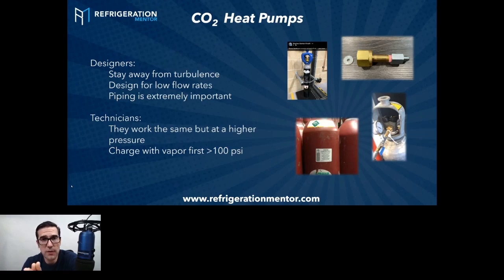In the buffer tanks - assuming you know how heat pumps are designed - you have cold water at the bottom and hot water at the top, something called stratification. If you have a lot of turbulence, it's going to mix up the hot and cold water. You want to take the cold water off the bottom; there's about a foot of mixed water above it, and then hot water above that. But turbulence will mix that up, and you won't have good quality water, because you want the coldest water possible going into the heat pump so you get a higher outlet temperature. To hit 70 or 80 Celsius, you need really cold water going in.